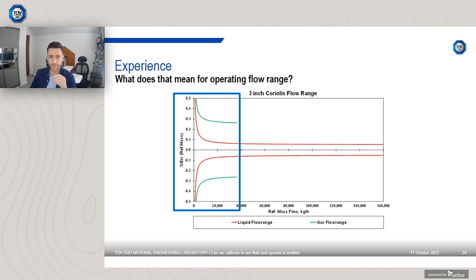Now, if you're only operating up to 36,000, are you only going to calibrate your device in water up to 36,000 kilograms an hour? Because that's very low velocity for a 3 inch Coriolis meter, and ultimately it means you would be calibrating down the very low end of a Coriolis meter, even though when it operates in gas, it would be operating up the higher end. It's just with respect to mass flow.